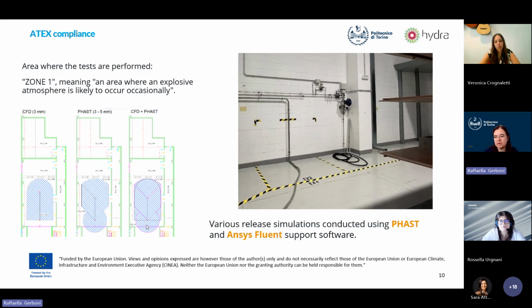One of the activities we carried out in order to use pure hydrogen in the wind tunnel was an ATEX study. The main part of the test room is ATEX Zone 1. Zone 1 is an area where an explosive atmosphere is likely to occur occasionally. We are sure there will be an explosive atmosphere, but it only happens sometimes, when we do the test, so this is compliant with the definition of ATEX Zone 1.